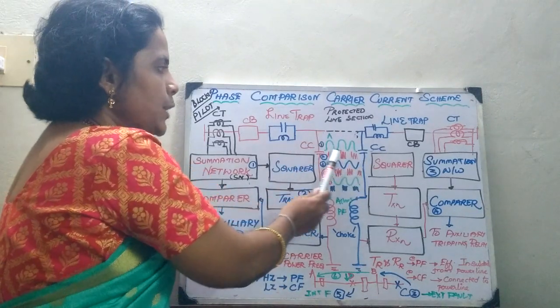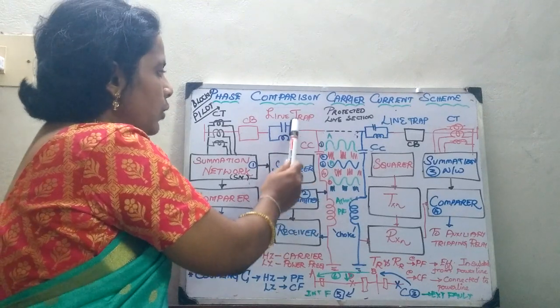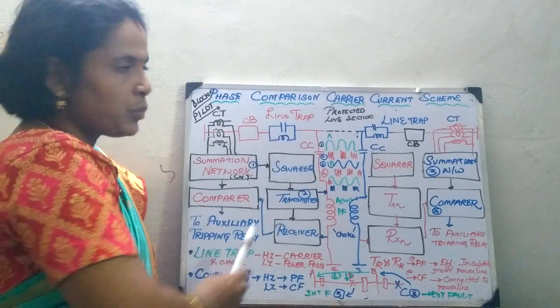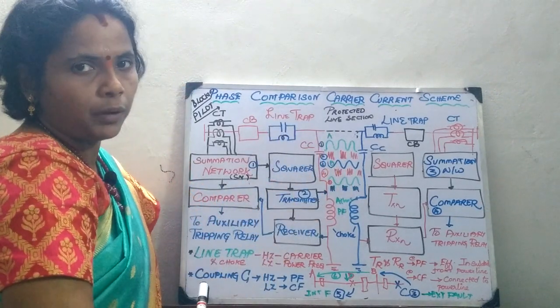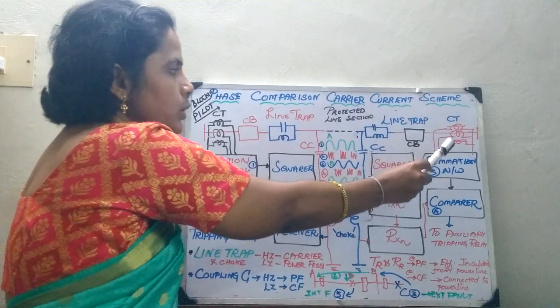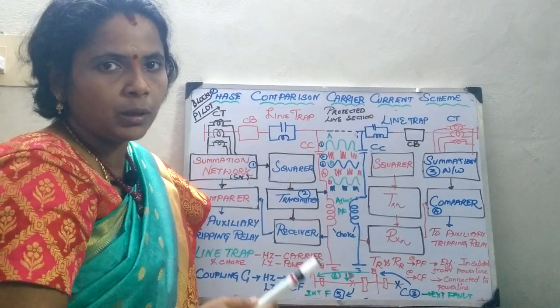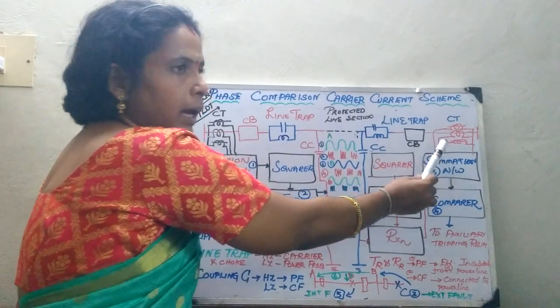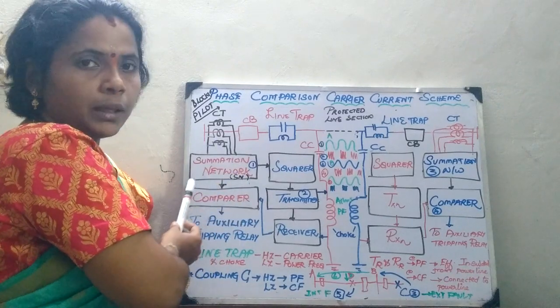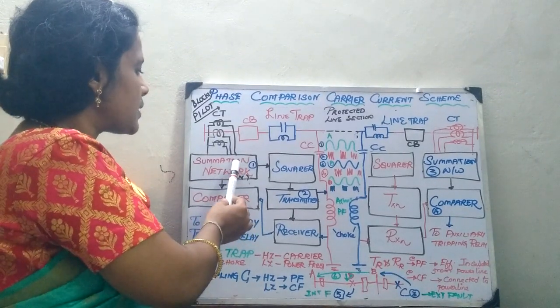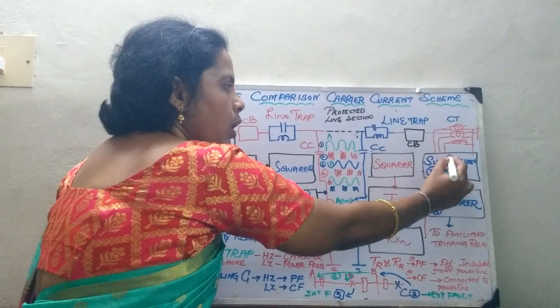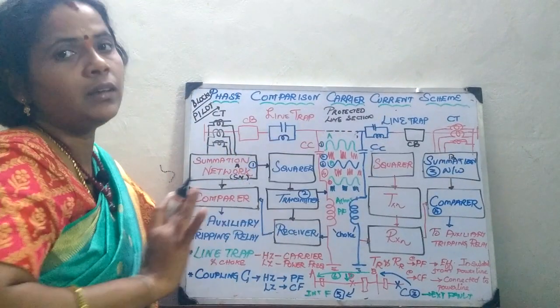This is the line to be protected. On one side you have a parallel resonance circuit, which is the line trap, connected in series to the line. There is also a circuit breaker, and on both sides current transformers are present to receive the current. Since the CTs are connected at both ends, the currents get reversed. Whatever current is summed up in the summation transformer, let us consider one end as A and the other as B.